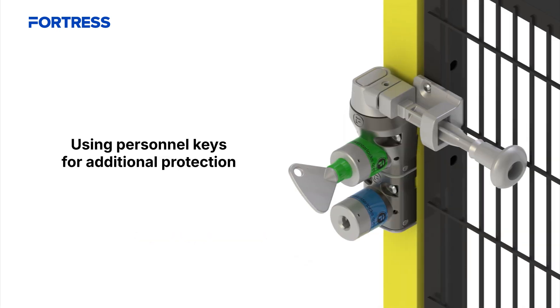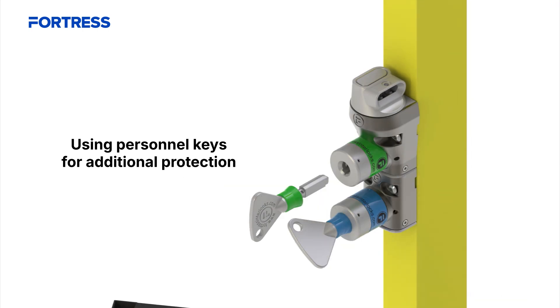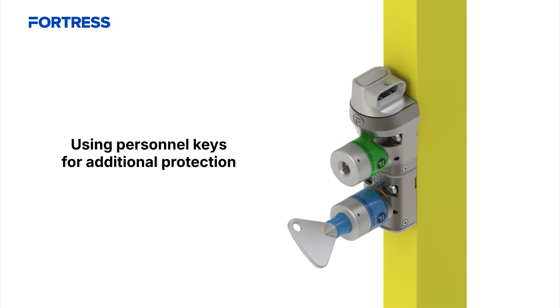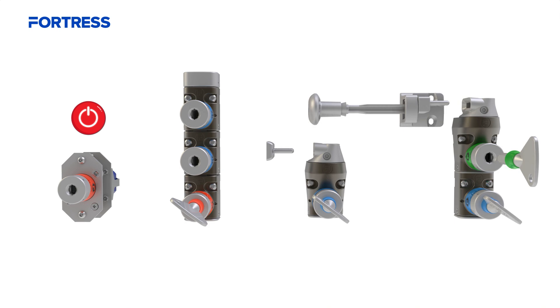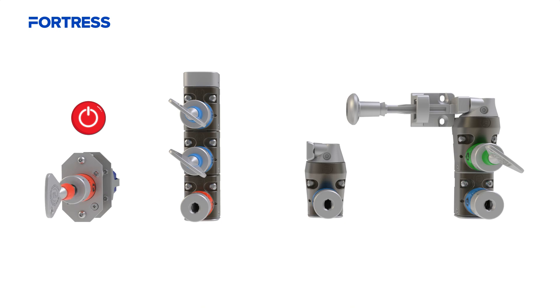For added safety, a personnel key can be used. The operator keeps this key with them inside the safeguarded space, and until it is returned, the access key remains trapped and the access lock cannot be closed. The defined process requires exact reversal to re-energize the hazardous energy or to restart the machine.